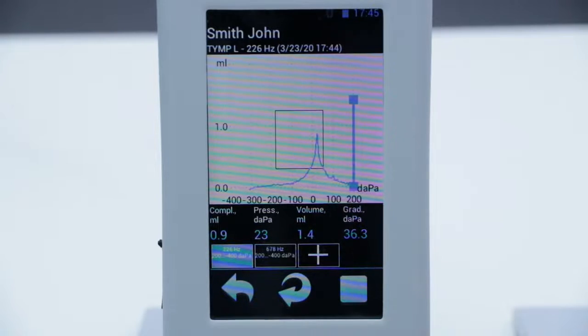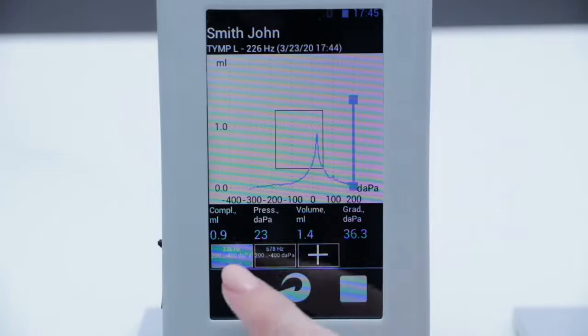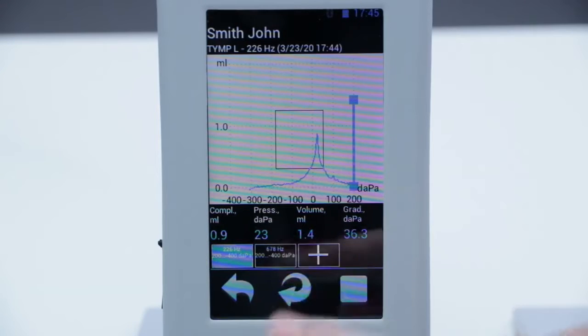Except the morphology of the result tympanogram, the doctor can also see the automatically estimated indices of compliance, pressure peak, volume of outer ear canal, and the gradient of tympanogram. For simplification of interpretation of the tympanogram, the system gives us the window of normative data set for pressure peak and for indices of compliance, for frequency of probe tone of 226 Hz.